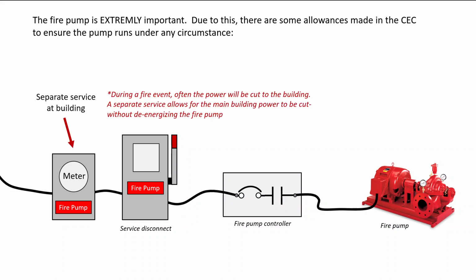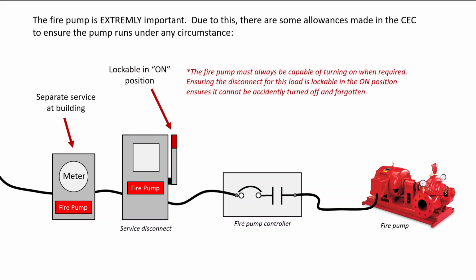First, the separate service at a building. During a fire event, often the power will be cut to the building. A separate service allows for the main building power to be cut without de-energizing the fire pump. A main service disconnect lockable in the on position. The fire pump must always be capable of turning on when required. Ensuring the disconnect for this load is lockable in the on position ensures it cannot be accidentally turned off and forgotten.